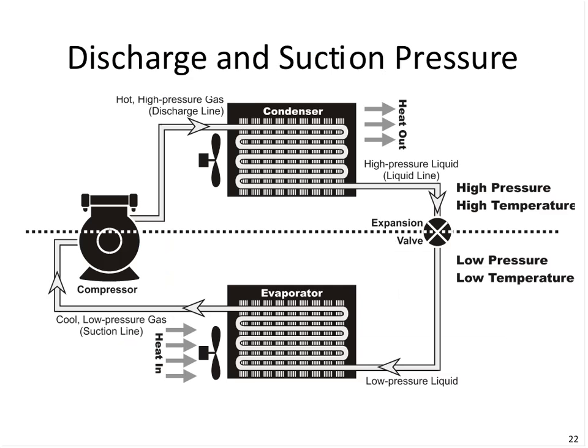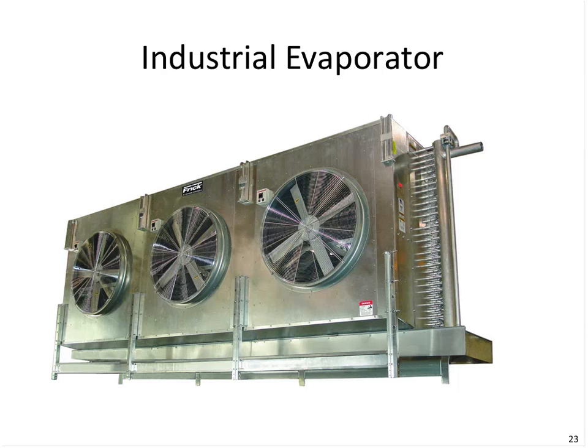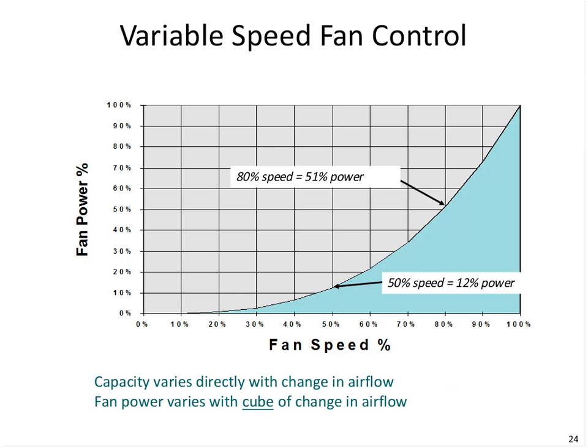So, back to our flow diagram here, and we're on this side of the system where we're adjusting the evaporator temperature and raising the pressure where possible to get the available energy savings. Here's a diagram of an evaporator where we have refrigerant entering the heat exchanger right here. The fans are drawing air from the space, cooling the air and discharging it over the product or through the process. Here we wanted to portray there's two areas of savings.